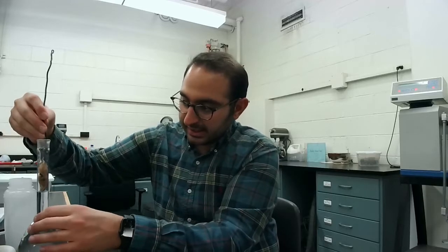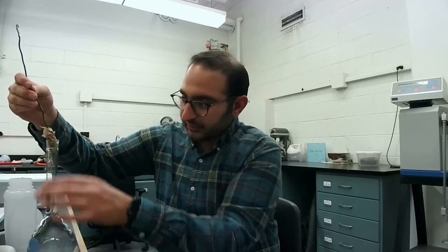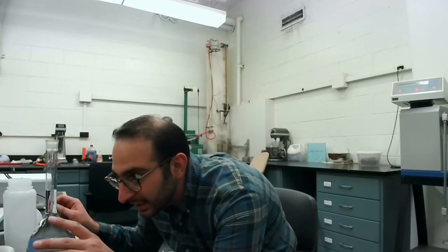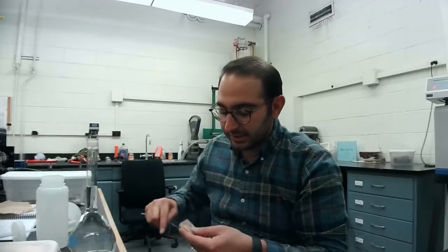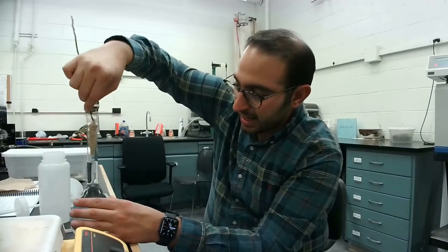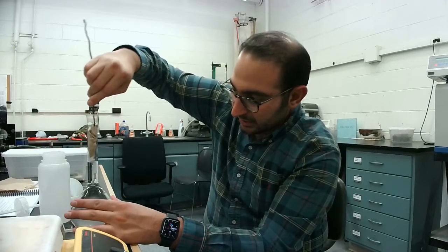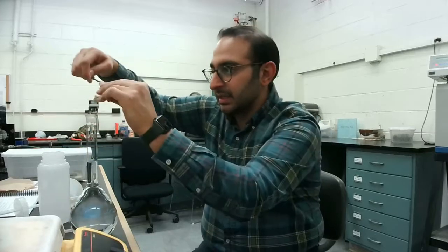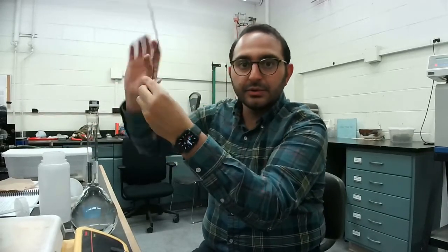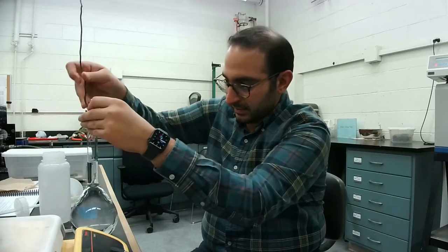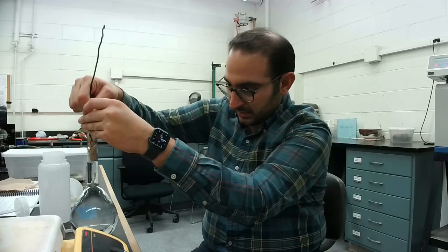Since you're measuring the mass, and the mass of this is really important for the calibration purpose, you also want to have anything on top of the calibration mark to be dry. So right now I'm seeing that the bottom of the meniscus is right at the bottom of that line. So all I need to do here is to make sure that the sides above the line are dry. I'm just going to dry out anything here on the sides. Make sure there's no wet surfaces. There we go.